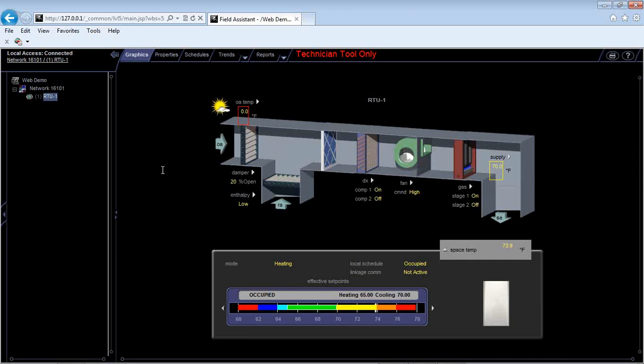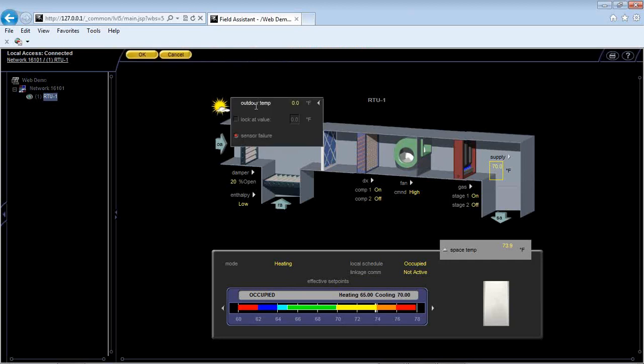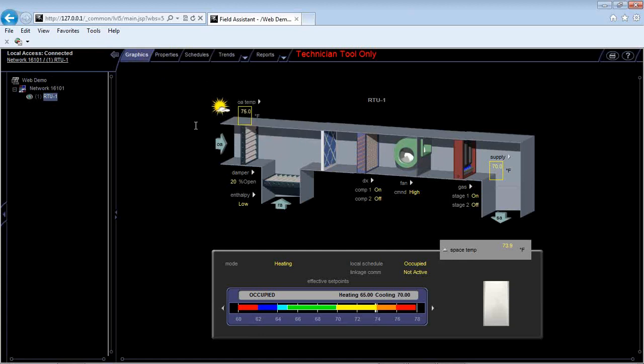And once it does that, I don't have an outdoor air temperature reading right now, but I can fake it. And let's say it's 75 degrees. Now I'm going to go directly to DX cooling and not use my economizer cooling, because I don't want to be economizing with 70-degree air. So you can see I switched to cooling. Now my compressor 1's on, okay?